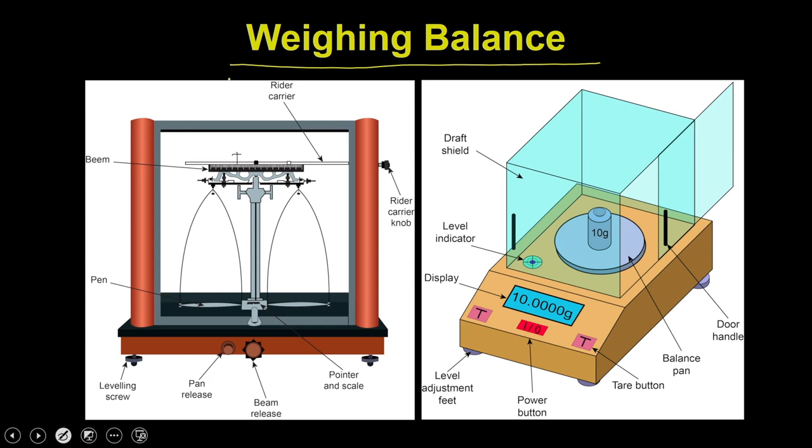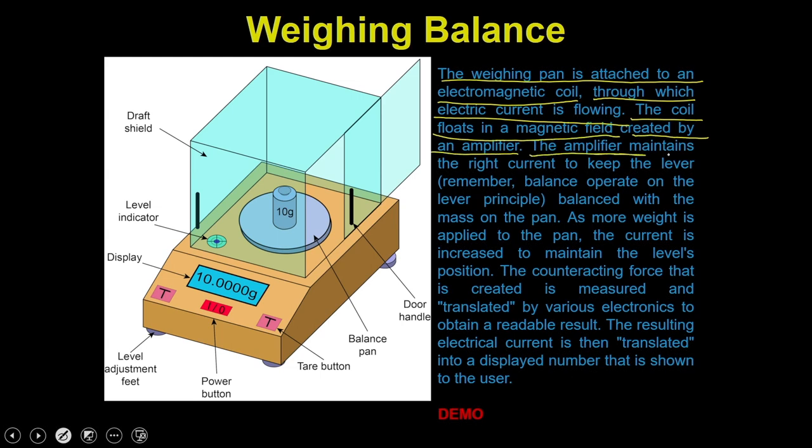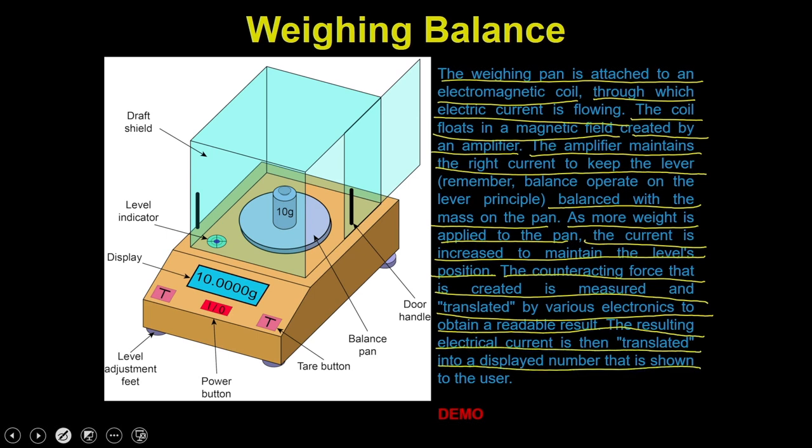Let us see how the digital balance works. The weighing pan is attached to an electromagnetic coil through which electric current is flowing. The coil floats in a magnetic field created by an amplifier. The amplifier maintains the right current to keep the lever balanced with the mass on the pan. As more weight is applied to the pan, the current is increased to maintain the position, and the counteracting force is measured and translated into a readable result displayed to the user.